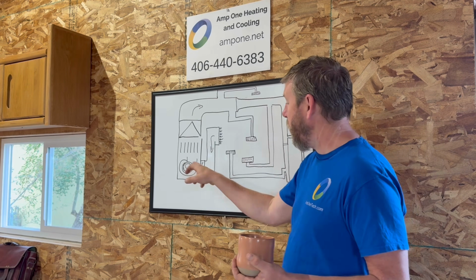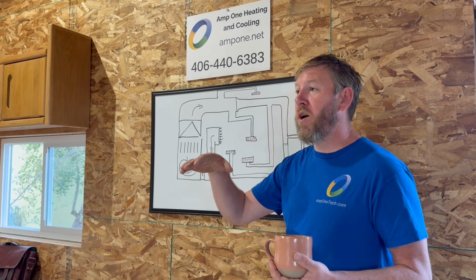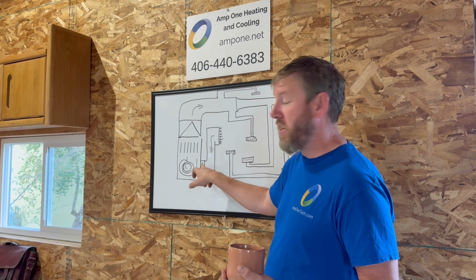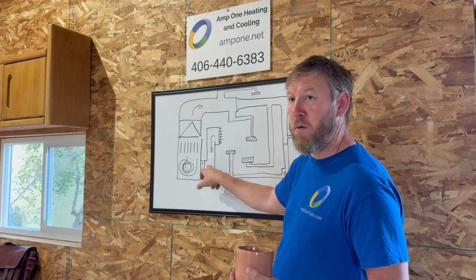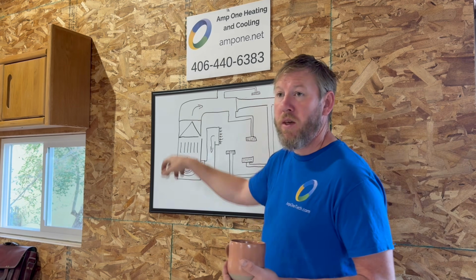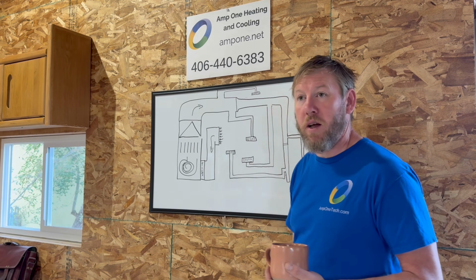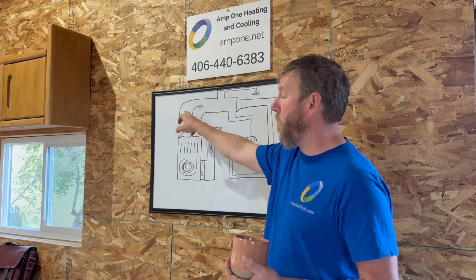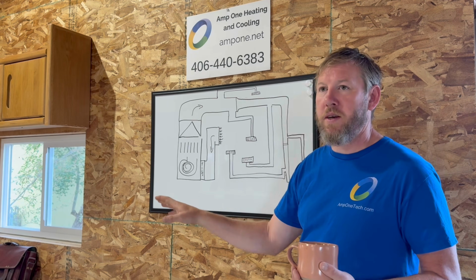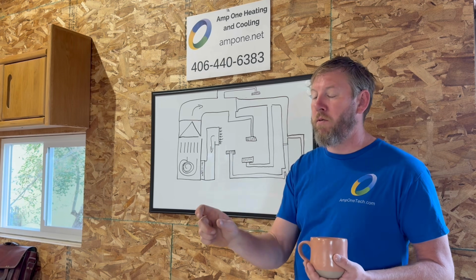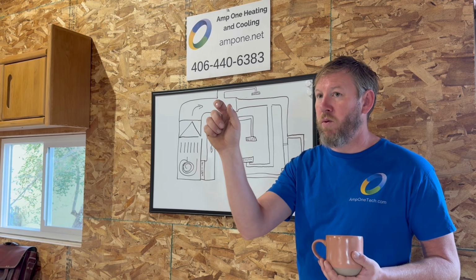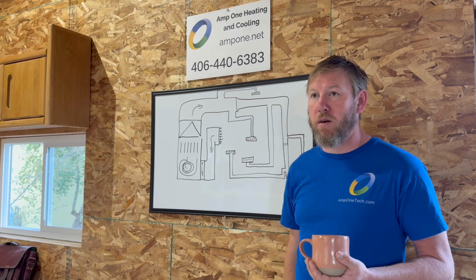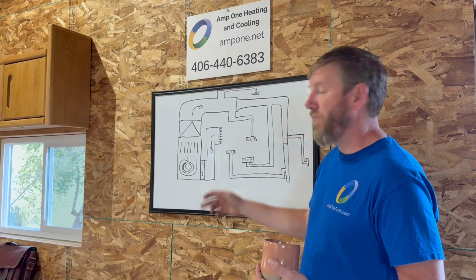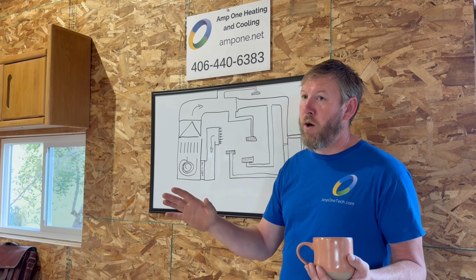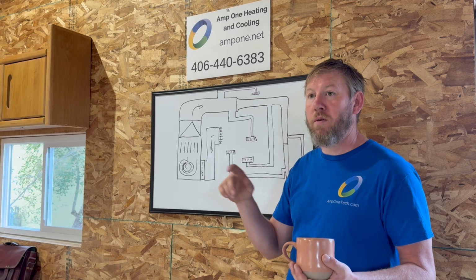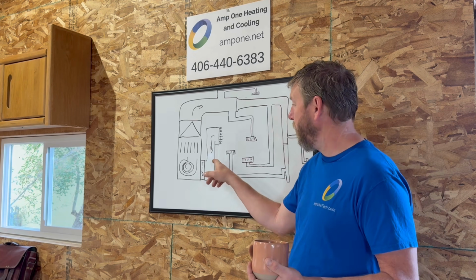Okay. Yeah. So once you do that, and your static pressure for that one, you take that reading, that pressure here and that pressure here. Usually on your low side it's going to be a negative pressure and a positive pressure up here. Don't pay attention to that negative, just drop it off. Take that and take the other one and you add them together.